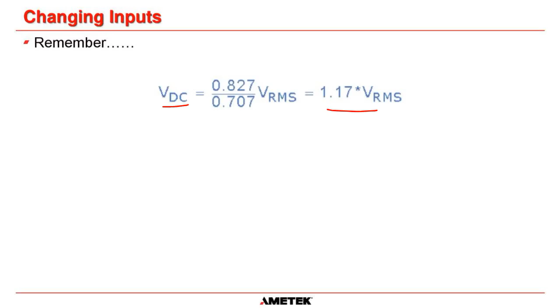Remember, volts DC is equal to 1.17 times the volts RMS. So if we had 480 volts going in and 130 volts on the secondary, it's saying that our volts on the output will be 152.1 volts DC if we used all diodes. You can see that all of these are diodes, so the calculation will be 152 volts.